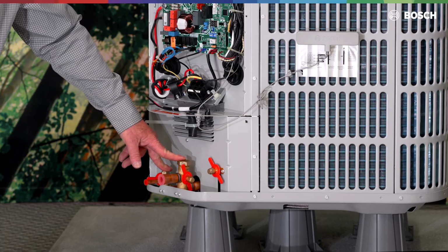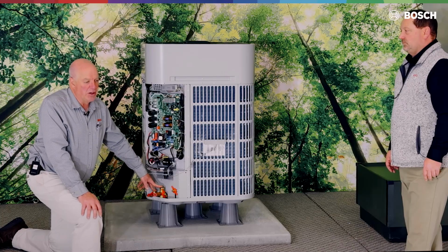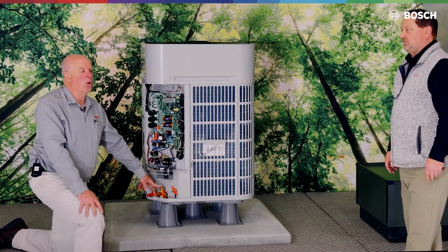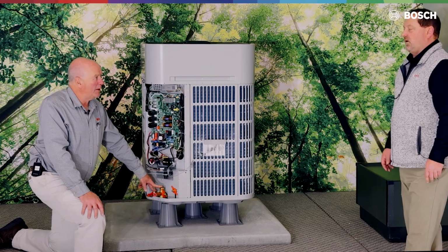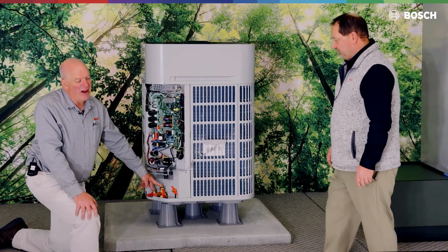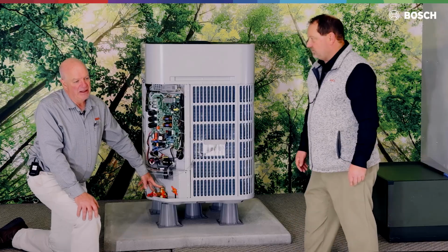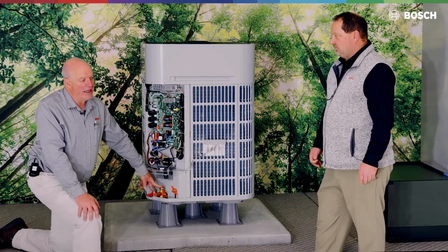Guys, when you open up these service valves, do not use a drill. Do not go crazy with it. There's a piano wire in there that stops the valve as you open. When you're pulling your vacuum, these valve caps need to be on that unit tight. If they're not on tight, you might have air leaking around the valve.